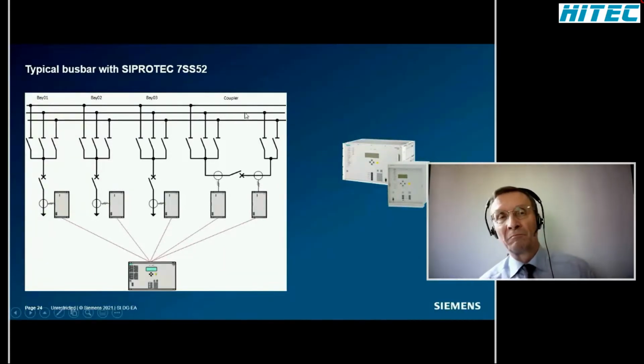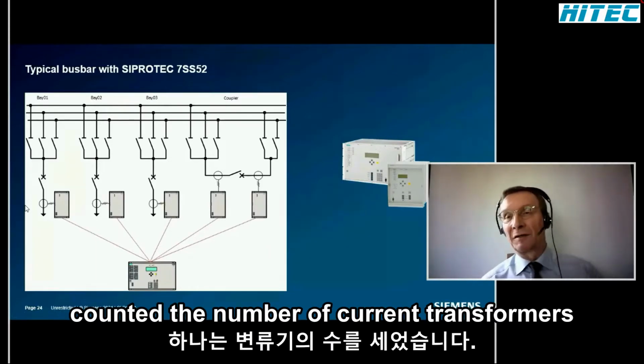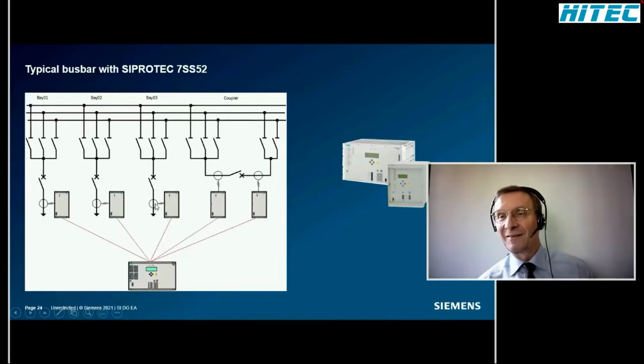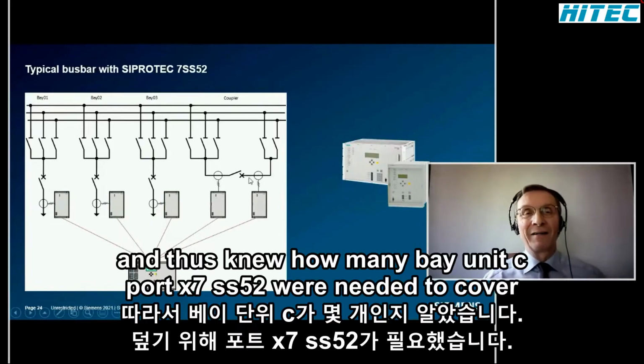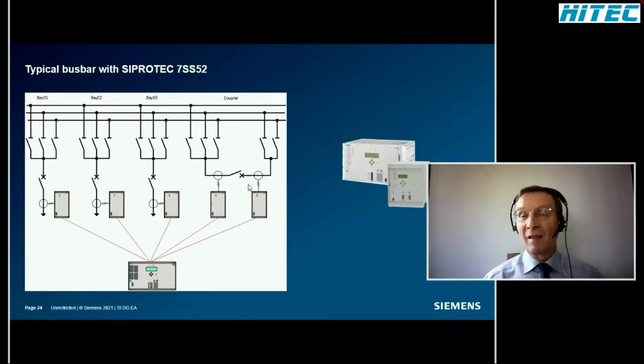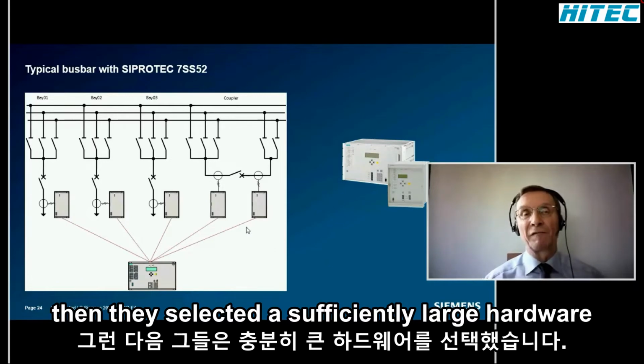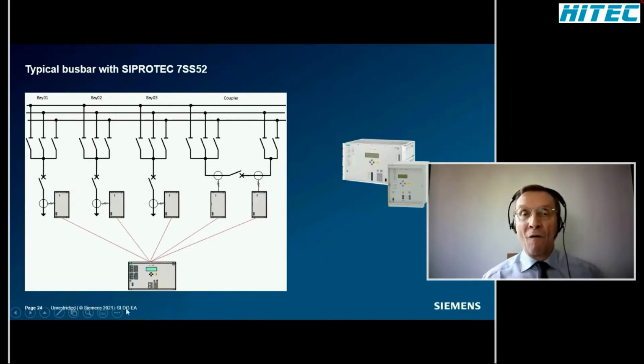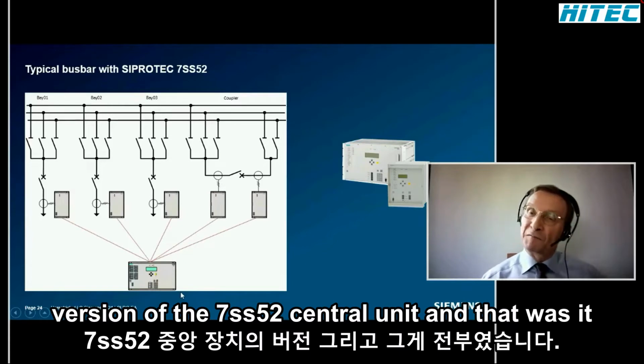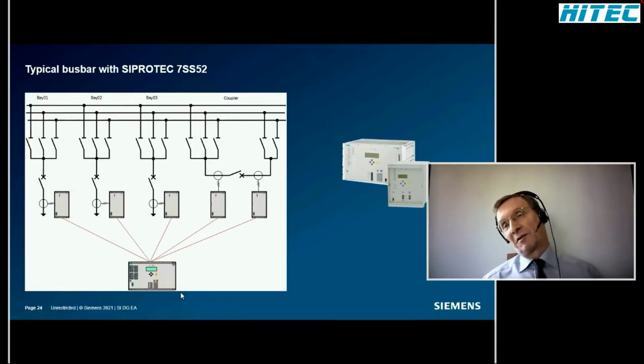This slide shows the single line diagram of a triple busbar as an example. To equip a system with SIPROTEC 7SS52 busbar protection, one counted the number of current transformers, and thus knew how many bay units SIPROTEC 7SS52 were needed to cover. Then they selected a sufficiently large hardware version of the 7SS52 central unit, and that was it.